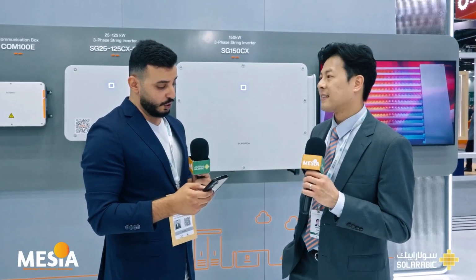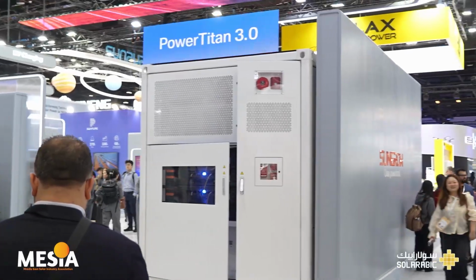What engineering measures does Sungrow take to avoid thermal derating, maintaining full power output even in outdoor temperatures reaching 55 Celsius? Some of our competitors start derating at 45 or 50 degrees. At Sungrow, our Power Titan series can achieve 55 degrees without any derating, providing full power output from the system.